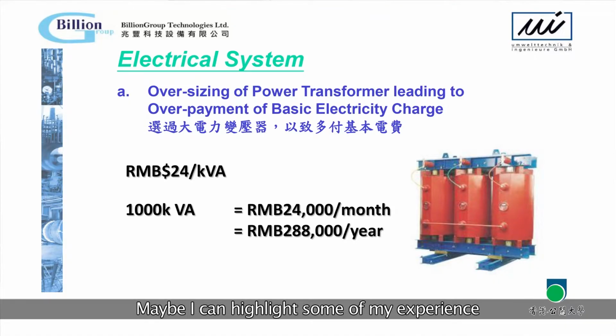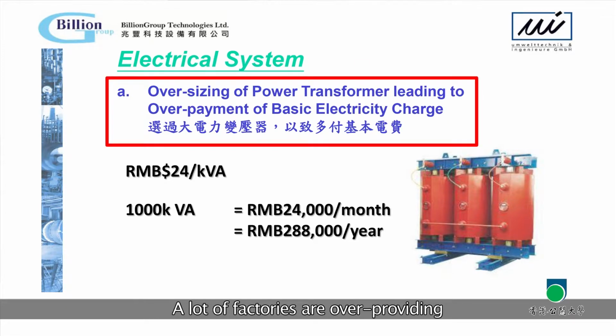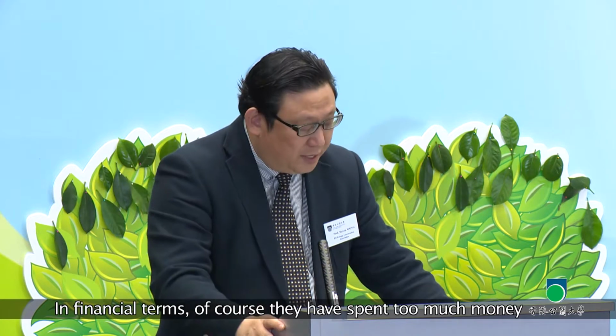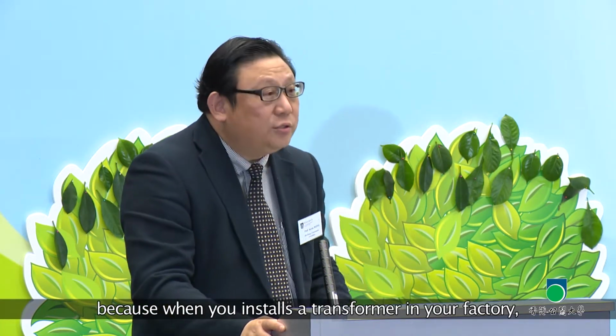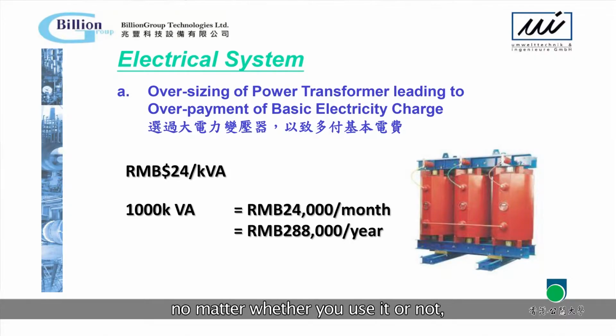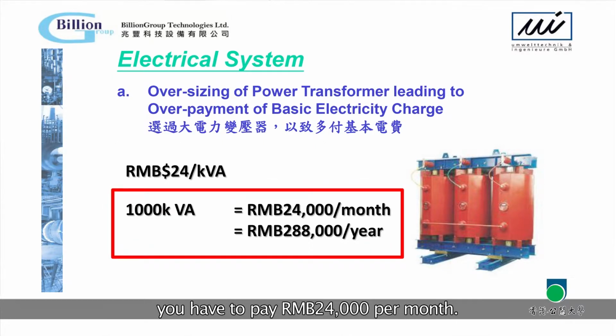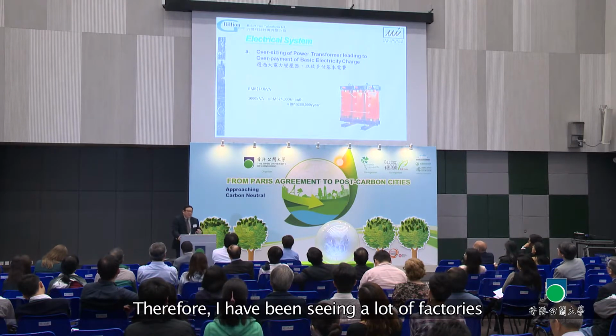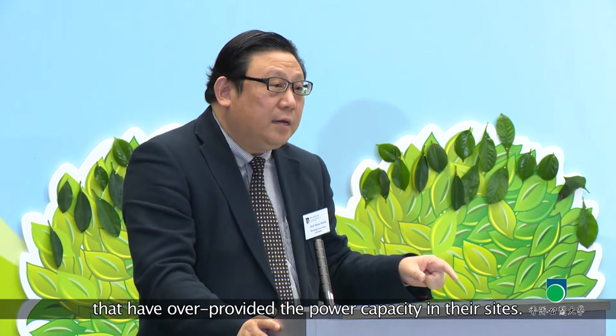Maybe I can highlight some of my experience, the shortcomings coming from the industry in the last two decades. On the electrical system, a lot of factories are over-providing the supply capacity in their factory. Financially, they've spent too much money, because when you install a transformer around 1,000 kVA, you have to pay 24,000 RMB per month, almost 300,000 every year. Therefore I've been seeing that a lot of factories over-provide the power capacity in their sites.